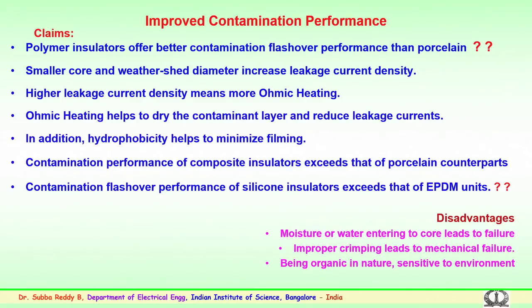In case of moisture or water, if there is damage to the insulating rubber on the surface of a polymeric insulator, water could enter the fiberglass core. This could lead to failure. There are reports of failures caused by moisture entering and the formation of nitric acid, and this nitric acid causing brittle fracture of the fiberglass rod.